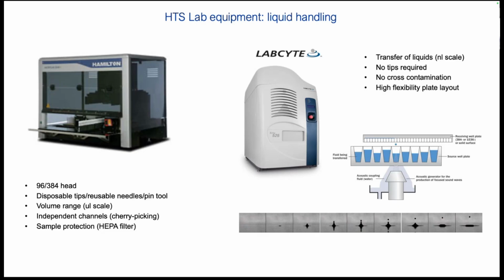Any cell will be disturbed if you don't wash it properly and if you don't fine-tune the parameters properly. There are some cells that are more sensitive than others. For example, you cannot wash 293s with an automatic washer because they fly away, since they are so poorly attached, unless you use coated plates or some tricks. But for a lot of other cells, we managed to find the sweet spot so that we can wash them and not detach them with the automatic handling.